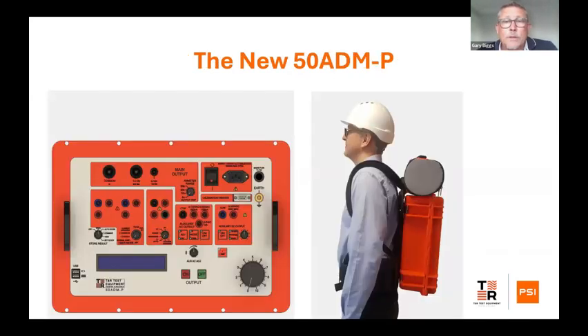Our new 50 ADM-P is the one that I wanted to concentrate on today and explain the functionality of it and why it can cross that boundary. Why can it test an old mechanical relay when a modern digital relay tester wouldn't be able to do that? But we can also have the finesse to test the more modern digital relays that have no burden. The new 50 ADM-P was born out of our old 200 ADM-P, and it was designed with one thing in mind: to be much smaller and lighter, but retain the VA ability to test older mechanical relays. In most countries you'll find there's still quite a number of older mechanical type relays, and they're still being manufactured and fitted to systems even in modern times because of their reliability factor.